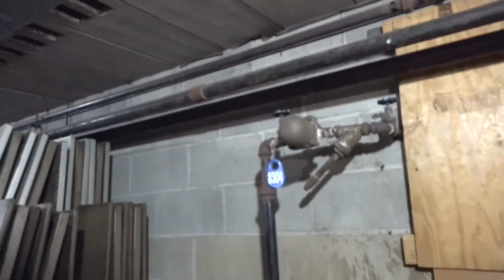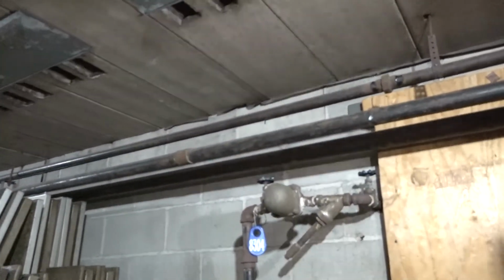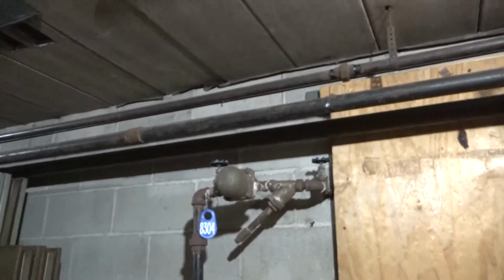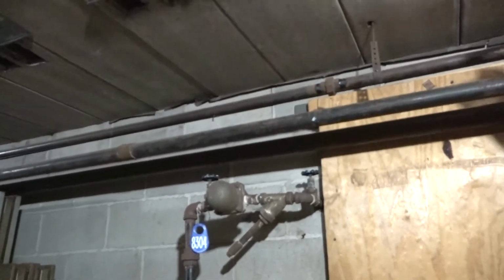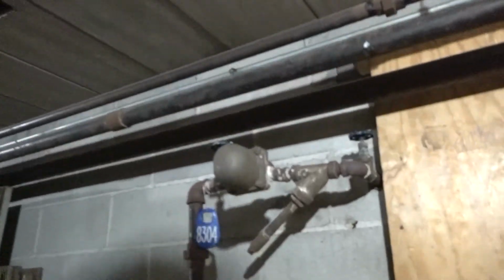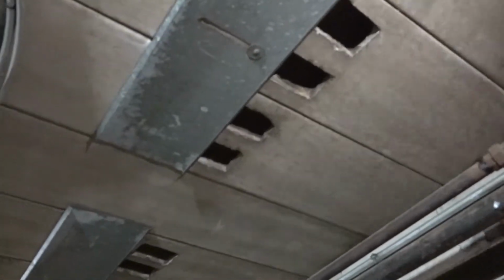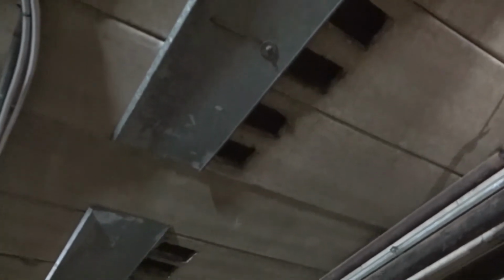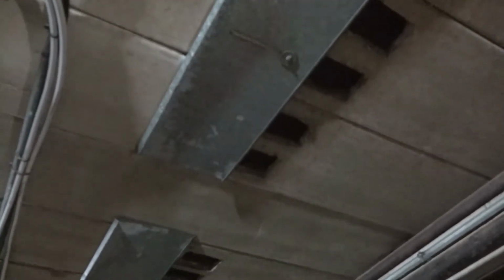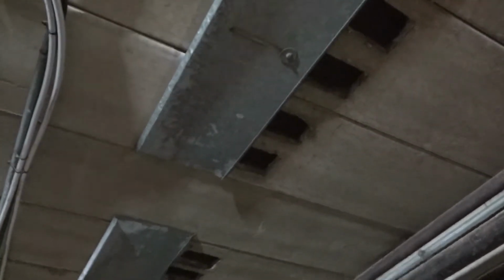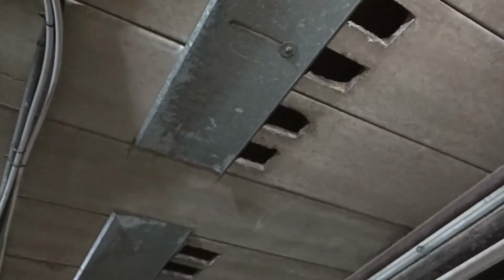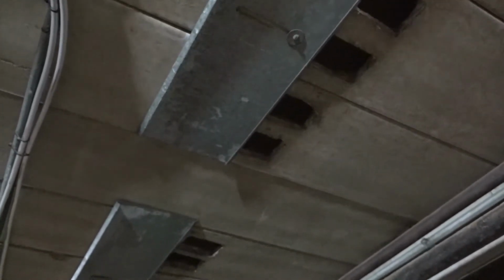Down there, it's hard to see these, but what happens is the fan blows the air out into the hallways and up through these holes in these floor beams. So these travel all the way across, say, the cafeteria and down the hall. The air comes up through a reheat coil in the space and then out into the classroom. So it's heated here, goes through the floor, then reheated again out into the learning space, cafeteria, classroom.